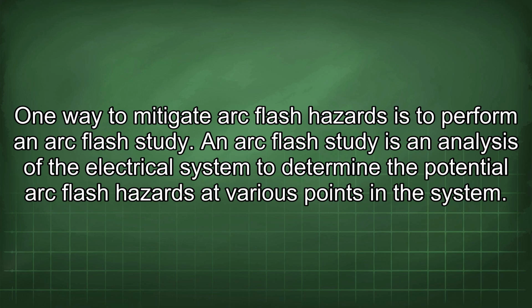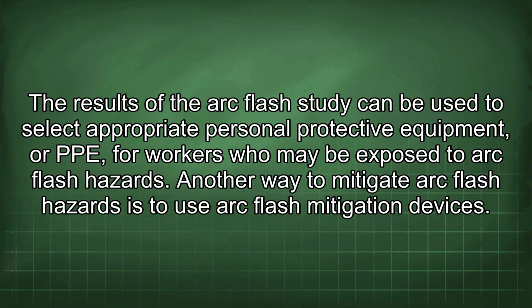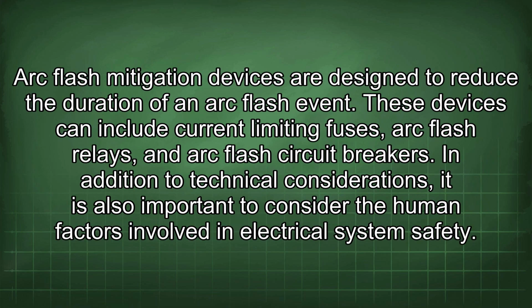An arc flash study is an analysis of the electrical system to determine the potential arc flash hazards at various points in the system. The results of the arc flash study can be used to select appropriate personal protective equipment, or PPE, for workers who may be exposed to arc flash hazards. Another way to mitigate arc flash hazards is to use arc flash mitigation devices. Arc flash mitigation devices are designed to reduce the duration of an arc flash event. These devices can include current-limiting fuses, arc flash relays, and arc flash circuit breakers.